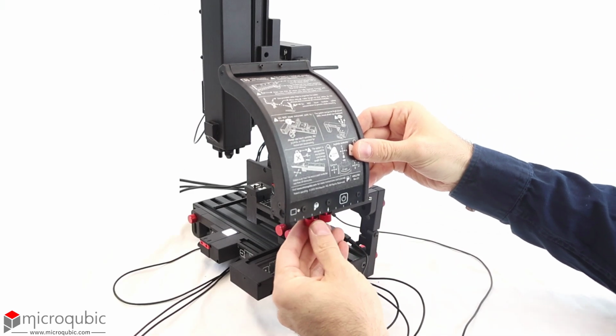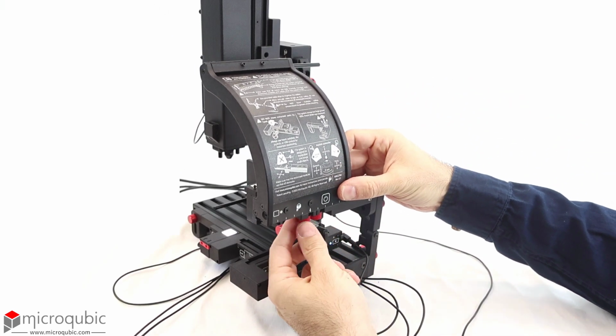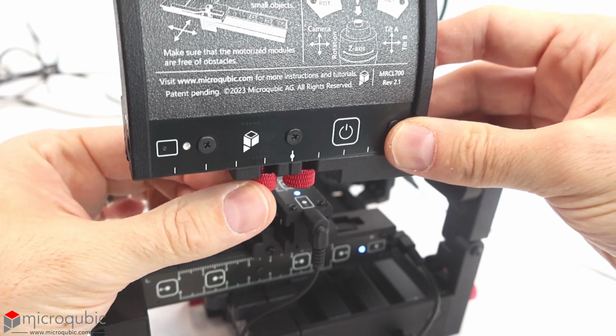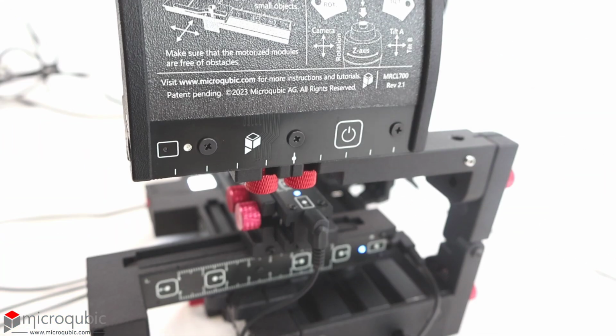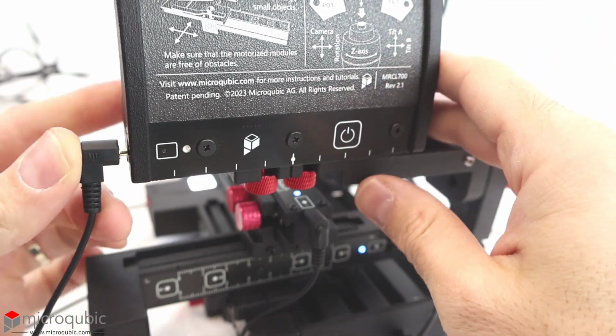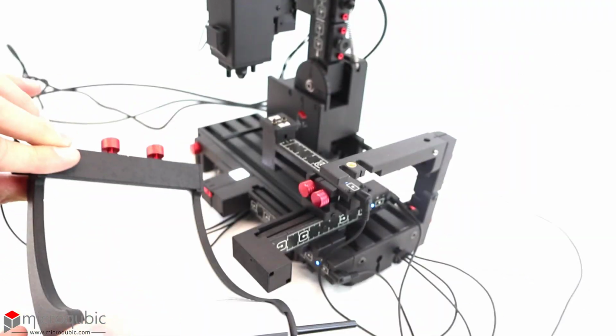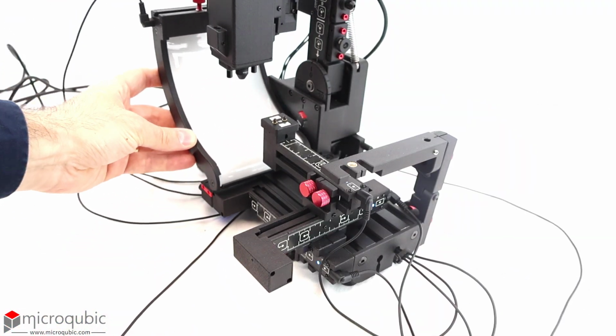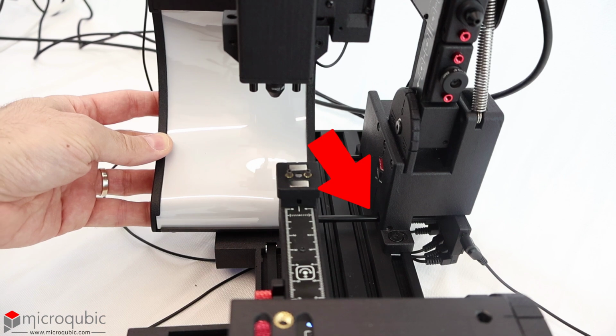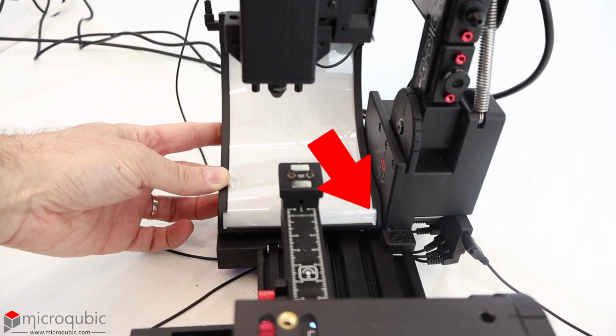Now, it's time to connect the curved illumination, which can be used to illuminate both opaque and transparent samples. For reflected light microscopy, the curved illumination can be fixed to the articulated arm using 2 thumb screws or by insertion. For the transmitted light microscopy, it can be placed under the sample by inserting the rod on its side into the conduit on the tilting module.